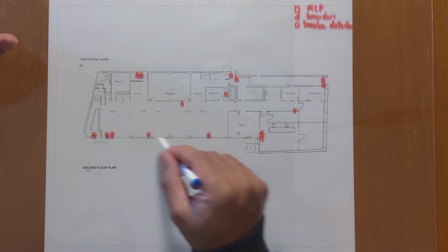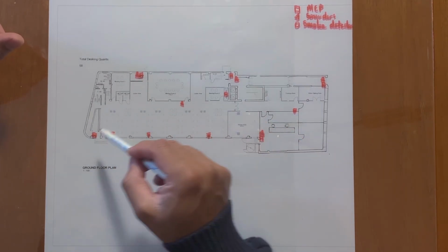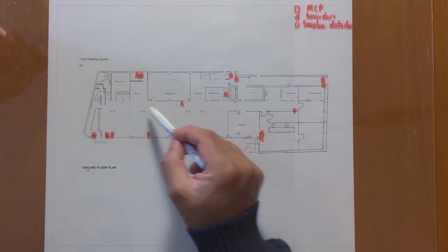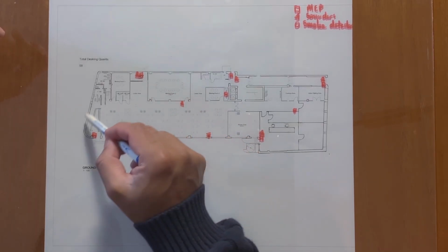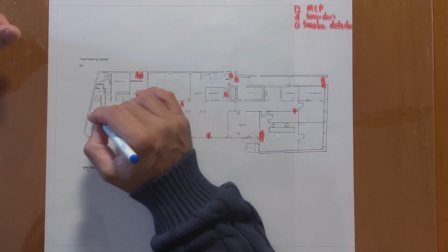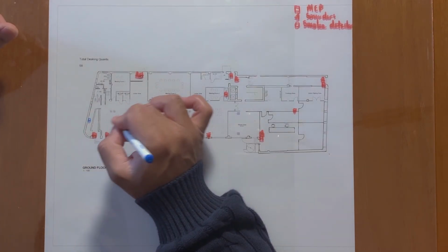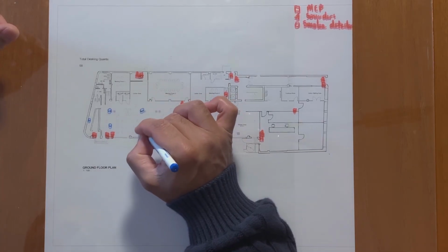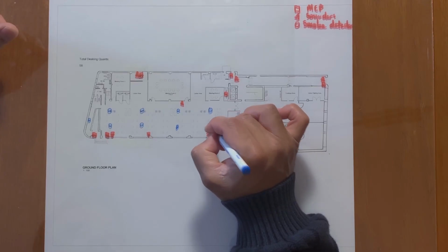This whole area here, because it joins onto it, is part of the escape route. So if I want to escape from here, I have to go out there, or maybe I'll run around this way and come down there, or around there. So we would have to put detection in this whole area. So this is part of the escape route. So I'll put one there. And then I'm not going to measure it all out, but roughly speaking, we'd put a detector there, maybe one there and there, and there and there.